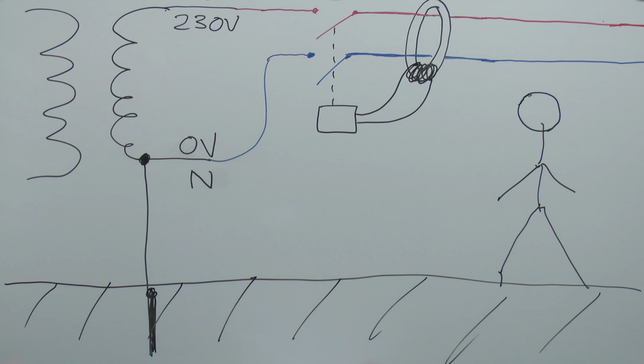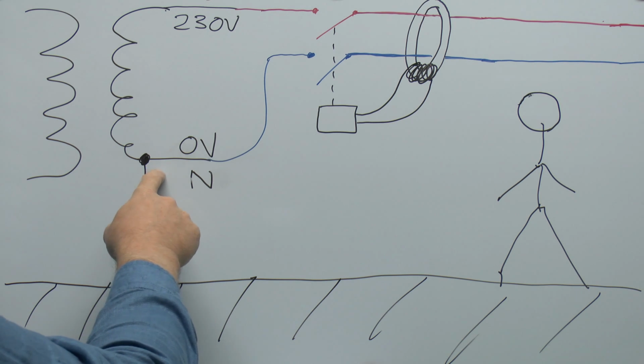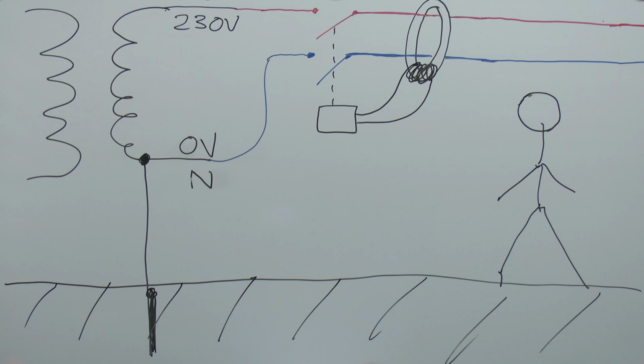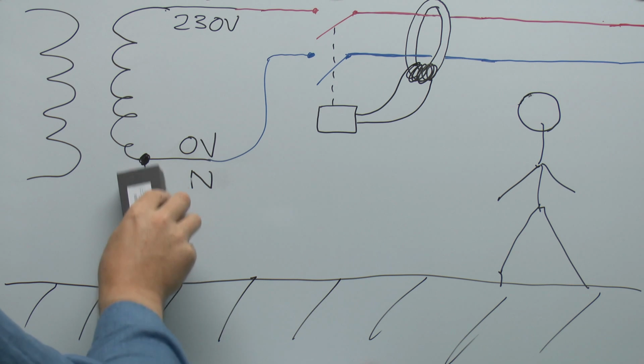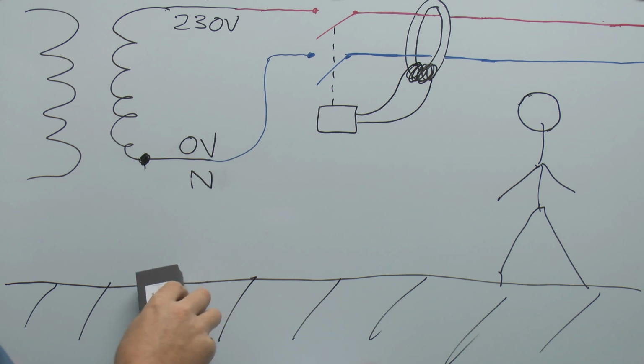Now, one vitally important point about RCDs is that they only work if the system itself is referenced to ground, and of course in normal mains supply that's exactly what it will be, because there's always a connection from the neutral to the actual ground itself. That's certainly going to be the case at the transformer, and in most cases there'll be multiple connections elsewhere within the system. But there can be instances where the system is not referenced to ground, so effectively this section here does not exist.